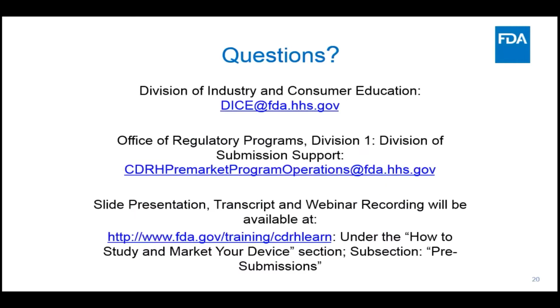Hello. Hey, thank you for this presentation. It was very helpful. Learned a few things that I hadn't heard of before. But I did want to ask a question about the timeframes for submission issue meetings. I was doing the math, and 60 days plus 70 days, that's 130 days. The 510(k) response letter is supposed to get in within 180 days. If you take 30 days to write things up after you meet with FDA, that only gives you till day 80? So if we get to the point where we're still working through issues, we suddenly realize we have an issue, we want to talk to the FDA, but we're past day 80. What would you recommend? Do we still try to get a submission issue done and hope it's going to get done faster than 70 days, or what would you recommend?